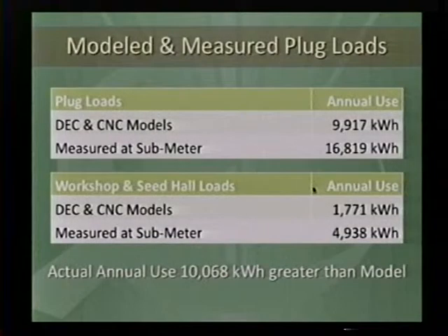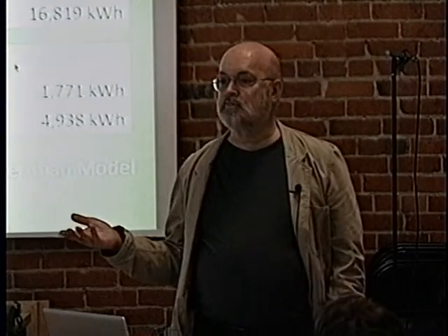In the workshop and the seed hall, we also underpredicted by a factor of 3 what the actual usage was. And you know, the plug loads are really based on what the client is often buying and using, but we found out a couple of other things. We had told the foundation to turn computers off at night. We've done some measurements. If you leave your Dell computer on and don't turn it off, over 13 hours at night, it'll consume a little over a kilowatt hour of energy. So with weekends and everything, that's about 365 kilowatt hours per year per computer. It adds up very quickly.